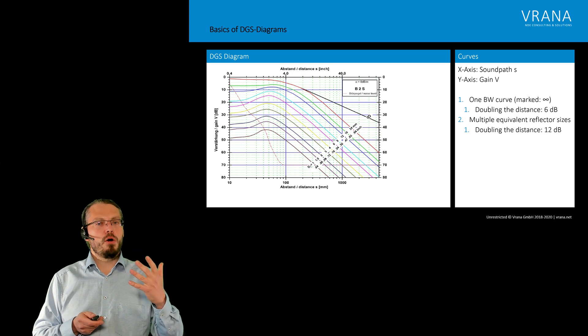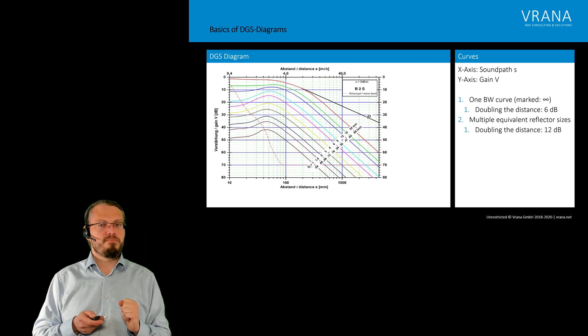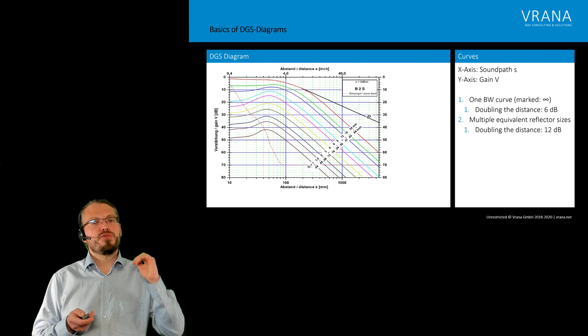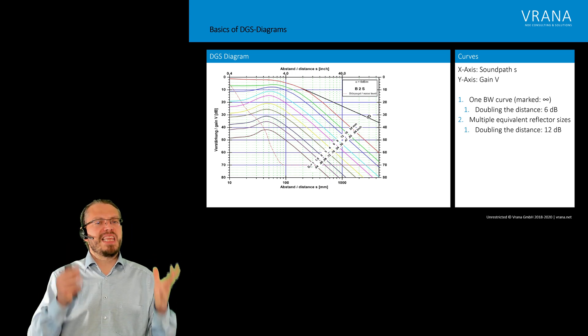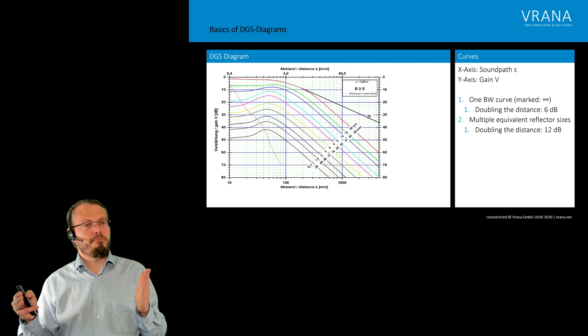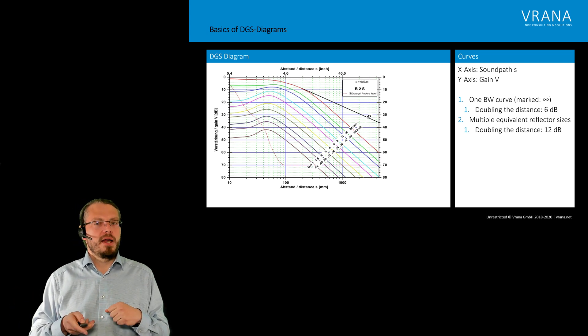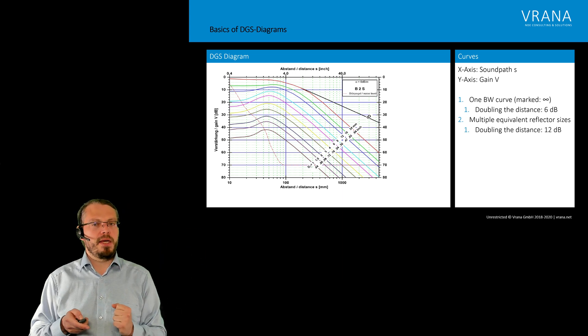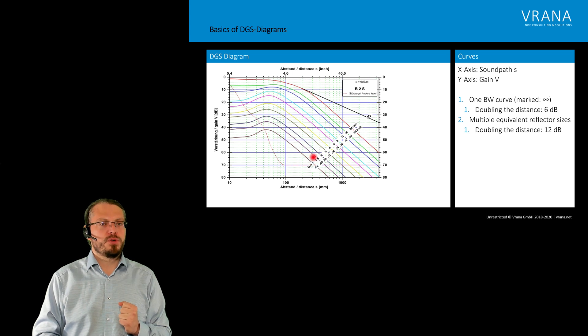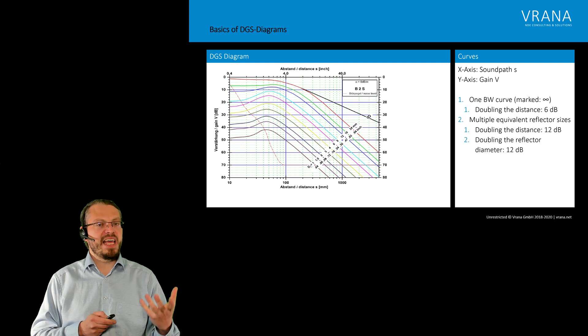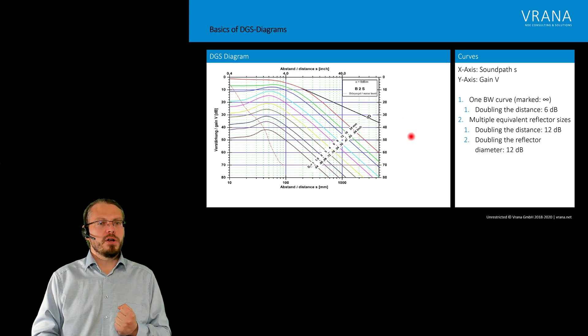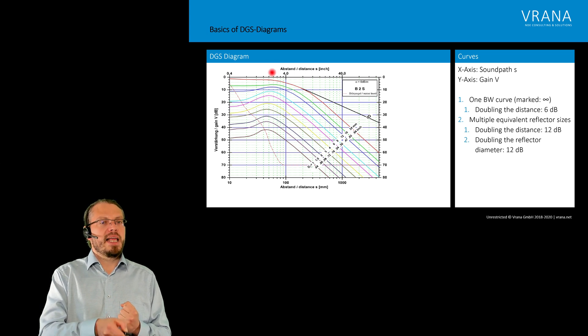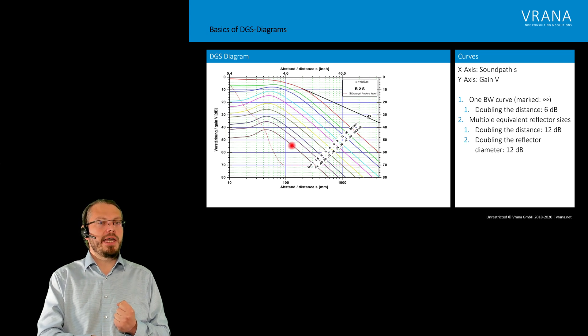We can already see that the slope of the other curves is steeper — here, if we double the distance we have a difference of 12 dB. Those curves represent different equivalent reflector sizes, or different flat bottom hole sizes, for different sound paths. We already talked about doubling the distance adding 12 dB, and going from the 1 mm curve to the 2 mm curve — doubling the reflector diameter — we also see a 12 dB difference. We can also see a peak here marking the end of our near field; beyond that we're in the far field.